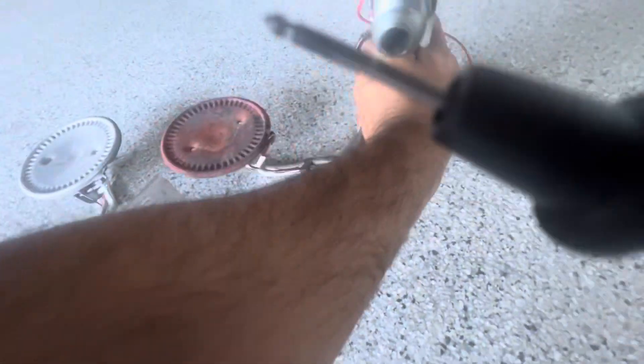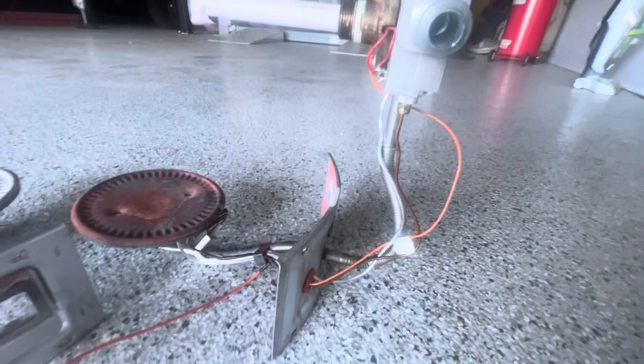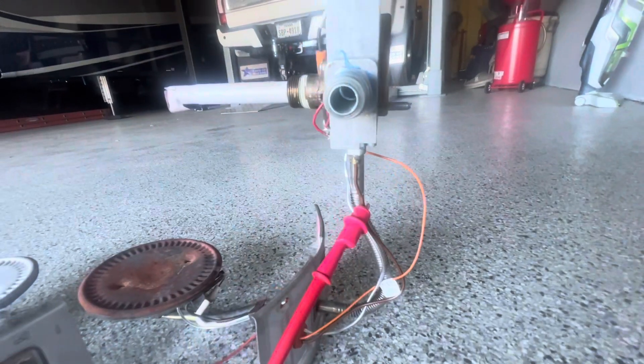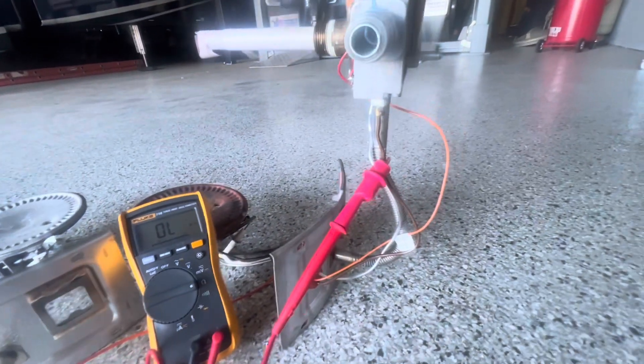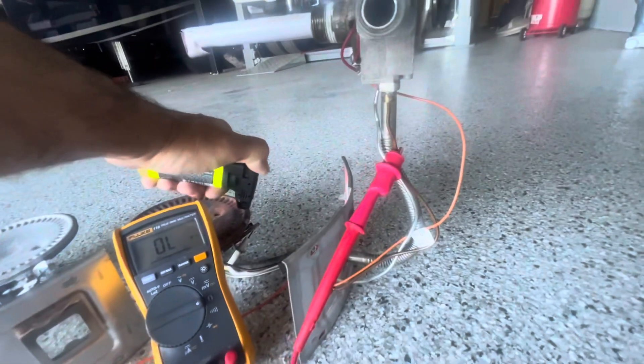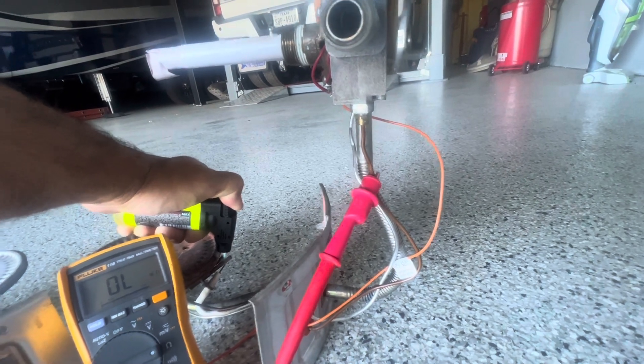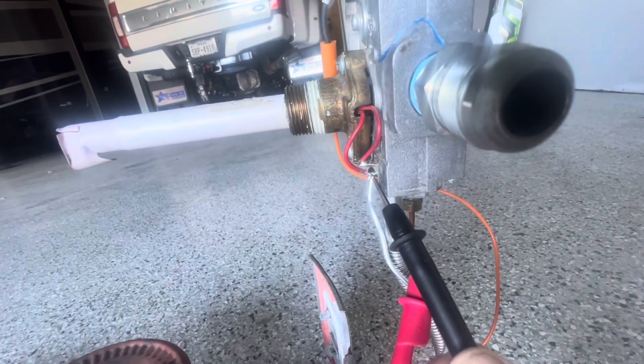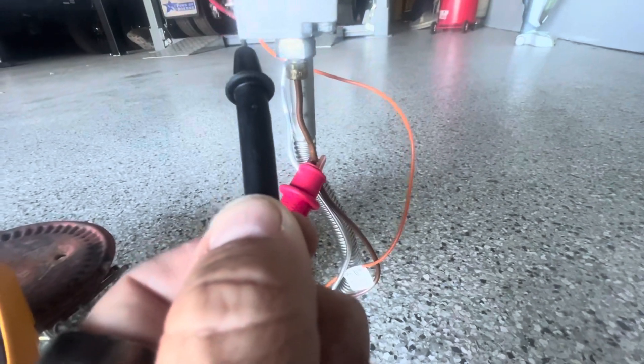Now let's talk about the easier way to do this. If you don't want to disconnect your thermocouple, put your alligator clip on the outside. And then I don't have three hands, so I'm going to do this. I'm going to heat this thermocouple up. And then I'm going to touch this little port on the bottom here. And there it is. So there's two little ports right here to the ECO. Go on the bottom one. Clip to your outer of your thermocouple. And then you are good to go.